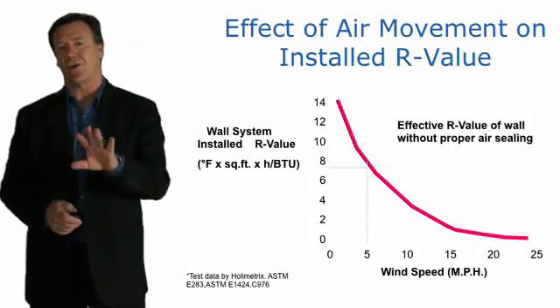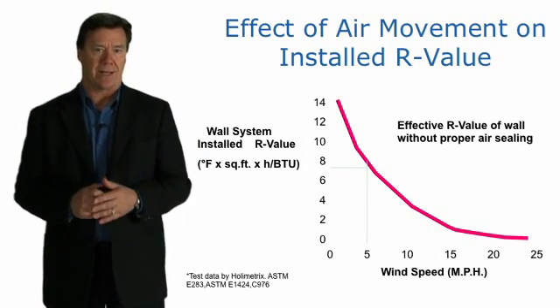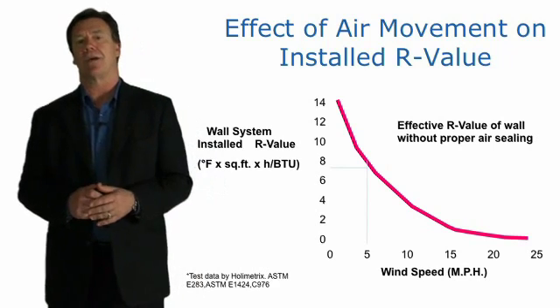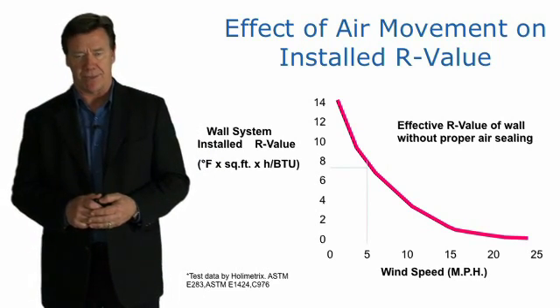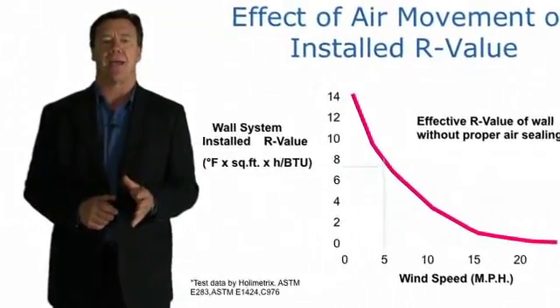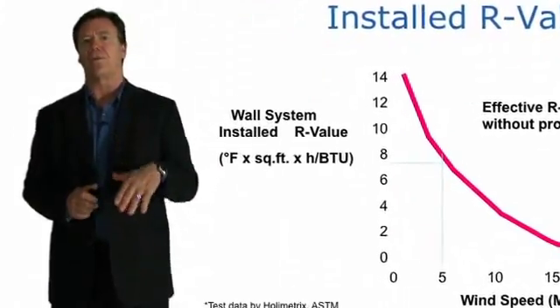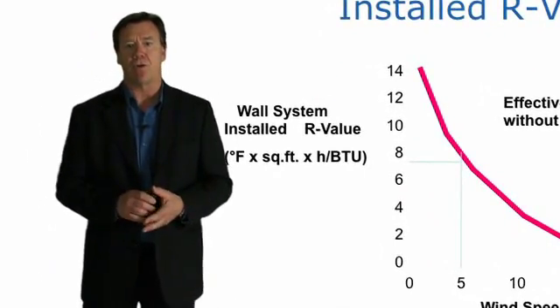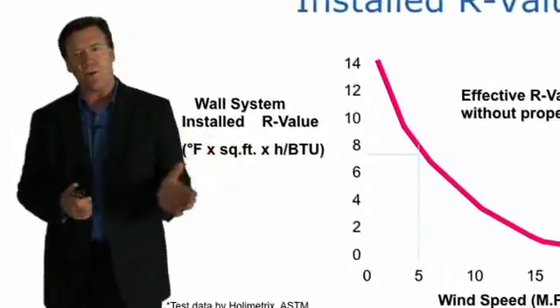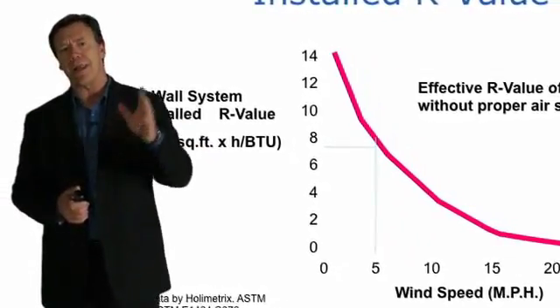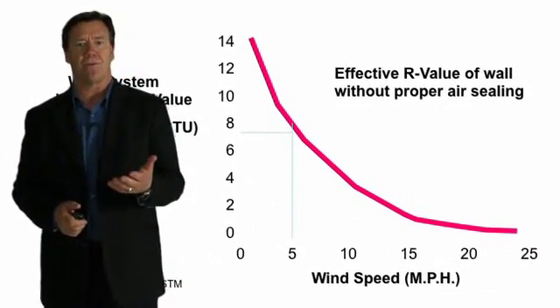This chart shows the impact of air infiltration on insulation. It's from a study done in the 1990s by a laboratory called Holimetrix. The vertical axis shows R-value from 0 to 14, and the horizontal axis shows wind speed. As wind speed increases, you can see how dramatically the R-value of the insulation drops.